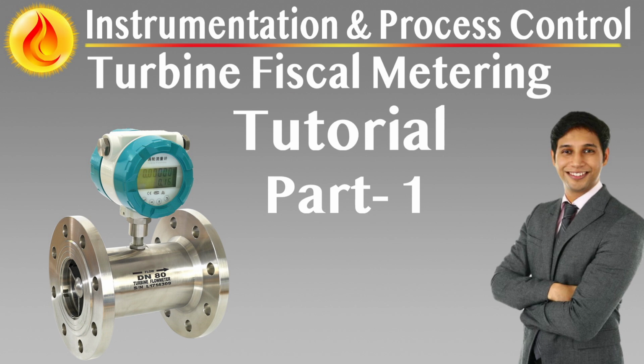Station manual as a diagnostic backbone. A dedicated station manual must be developed, detailing operation, calibration, validation, maintenance, and documentation procedures for every primary and secondary measurement device. This manual must cover signal transmission checks, statistical diagnostics, drift response thresholds, and alignment with fiscal audit requirements. It must be precise enough to allow repeatable actions and flexible enough to accommodate future instrument upgrades or regulatory changes.